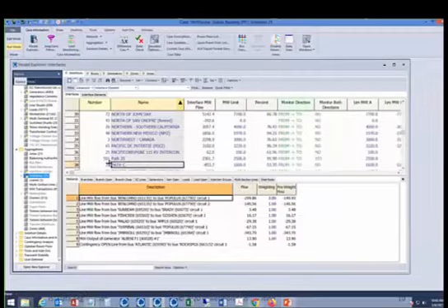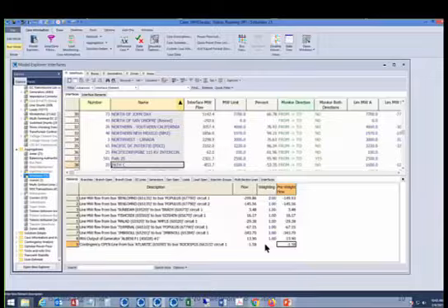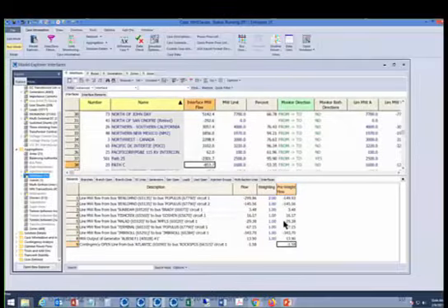And then I can see in my results for the interface that I just edited, that I put the contingency line open element in, it's got a contribution. So the contribution to the flow on these other elements, looks like I picked one that was nearby, but not really. It's only 1.5 megawatts, but it decreases the flow on the interface by 1.5 megawatts when you open that line. So that's what that calculation is telling you. And then it's reflected in the total and so forth.